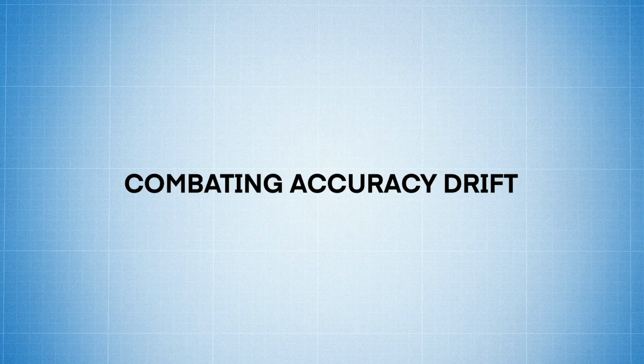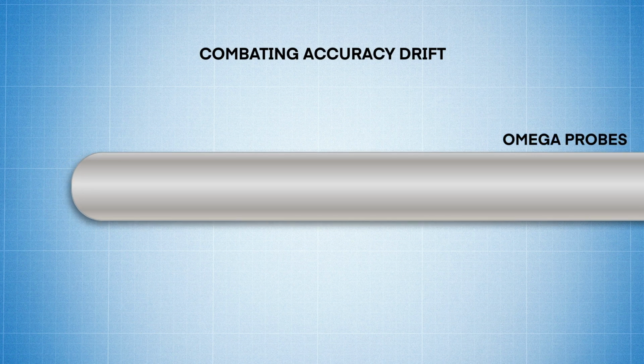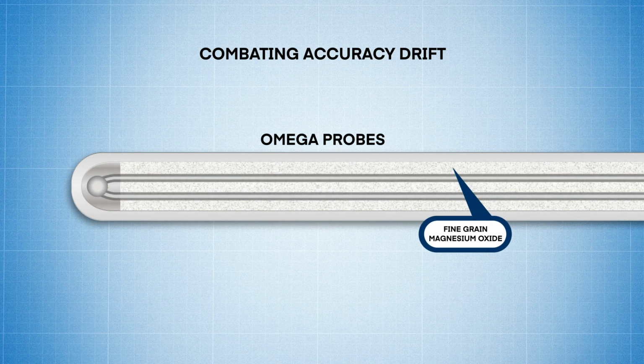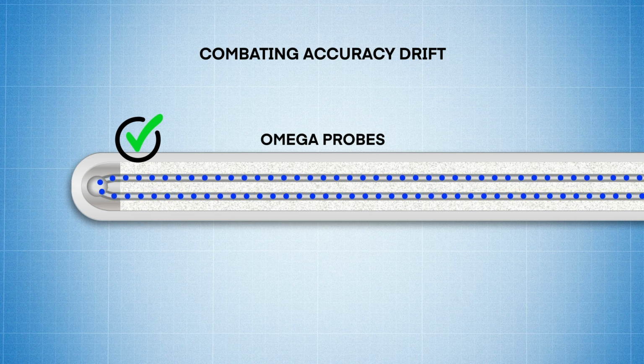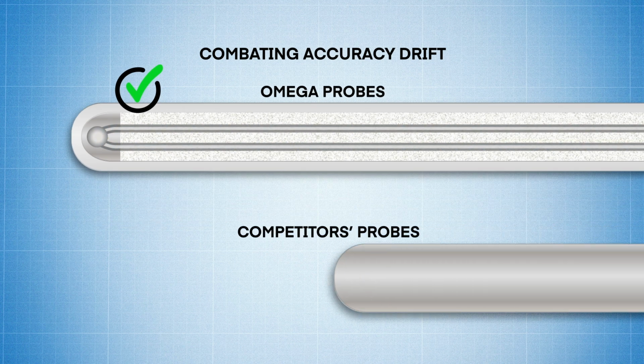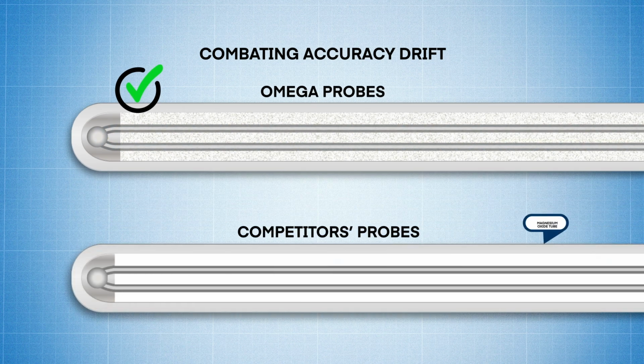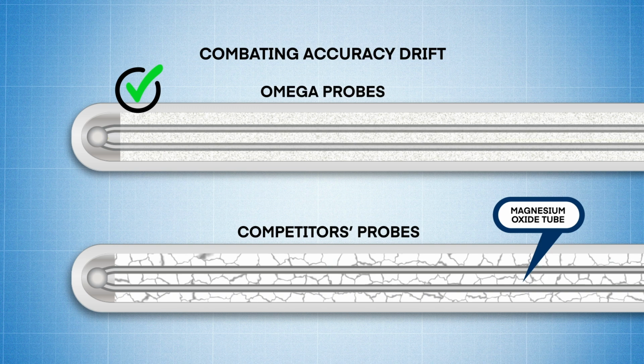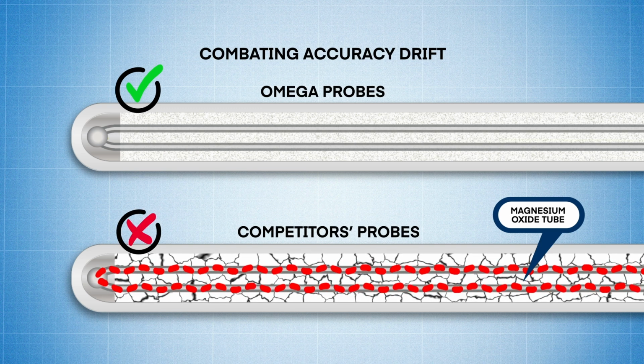As with any thermocouple probe, accuracy drift is the enemy. To combat accuracy drift, DwyerOmega only uses a fine-grain, high-purity magnesium oxide insulation, resulting in less stress on the thermocouple alloy wires during assembly, while our competitor's insulation starts as a rigid, pre-formed magnesium oxide tube that is crushed during the manufacturing process, putting much more stress on the alloy wires.